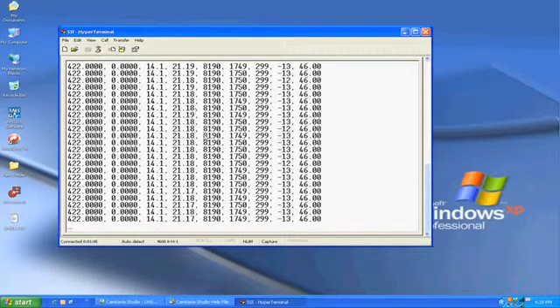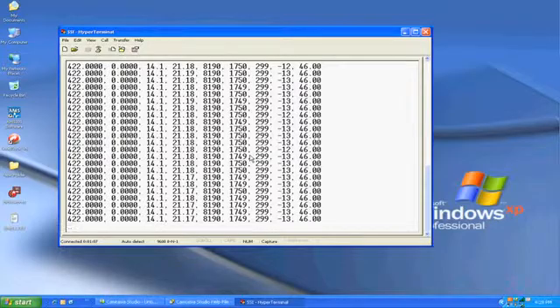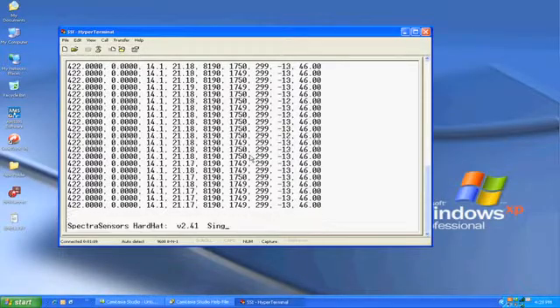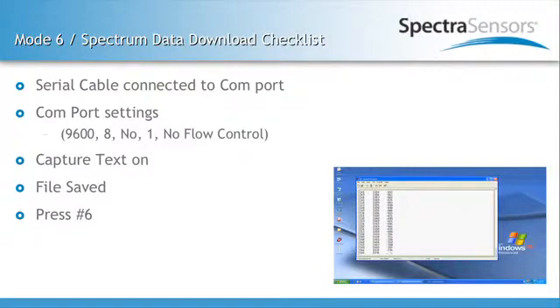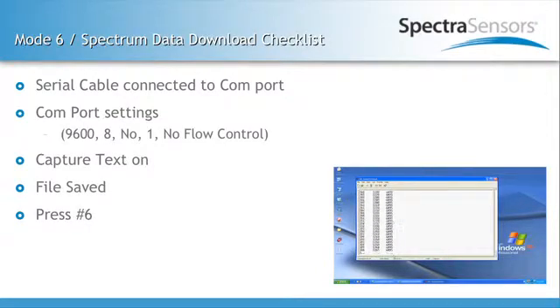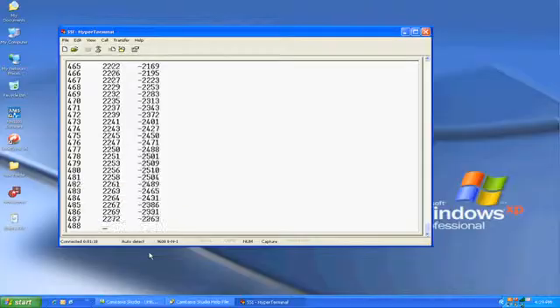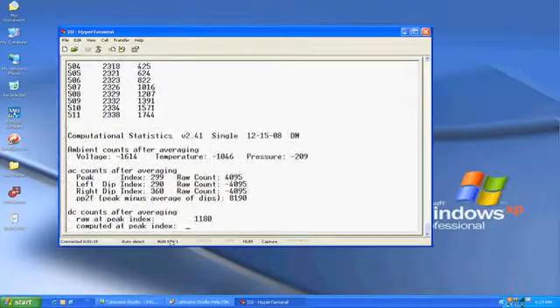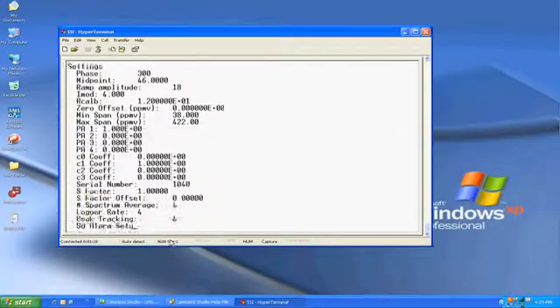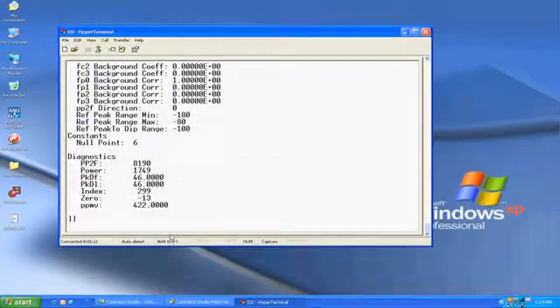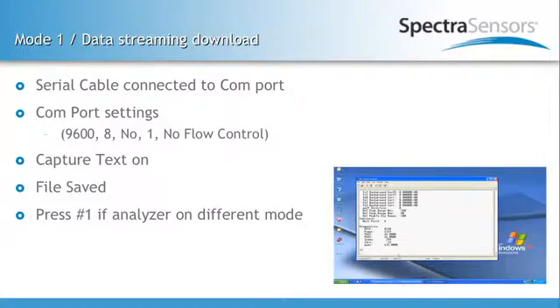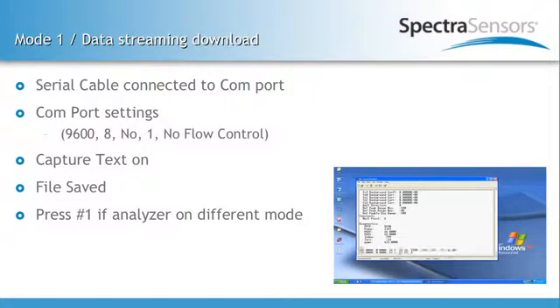Now, in order to get the mode 6 data, you press the pound 6 on the analyzer. Notice that the stream stopped for a second, and then the whole data would be downloaded until you get the spectrum and the parameter list. Once that's done, you press pound 1 to go back to the normal mode of operation, and your data stream will be back on.